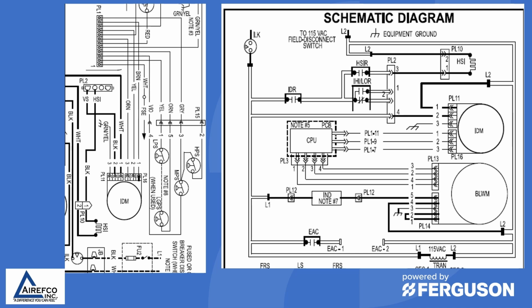A lot of your top-end gas furnaces today run inducer motors with ECM motors. And these motors, of course, have high voltage that is powering the electronics in the motor with L1, L2 with high voltage. And then you have various wires, depending on the ECM motor, that send communication to the inducer motor from the control board to run at different speeds for different modes of operation.